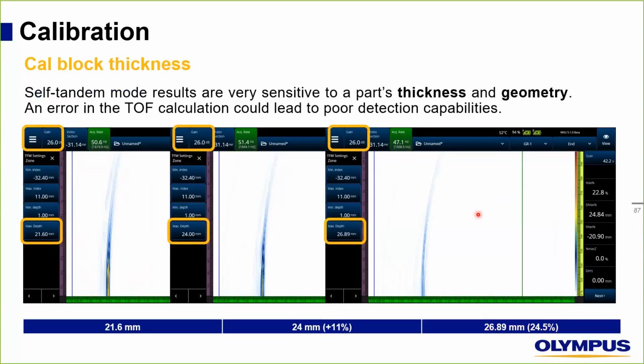Another demonstration, this time not on a side drill hole, but on a notch. So we have a notch at 21.6 millimeter, and we changed the thickness twice here, to 24 and to 26.89. And as you can see, for the right depth of thickness, or the right depth of the notch, sorry, we have a very good signal. We changed the thickness and we lost a lot of amplitude here. And here, we are almost about to lose our detection altogether. So again, be very, very careful when using the self-tandem modes, especially when you don't have the right thickness for the calibration block.